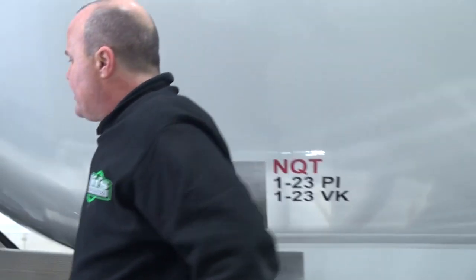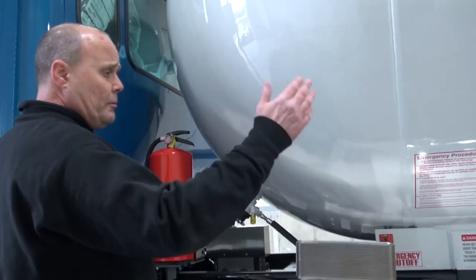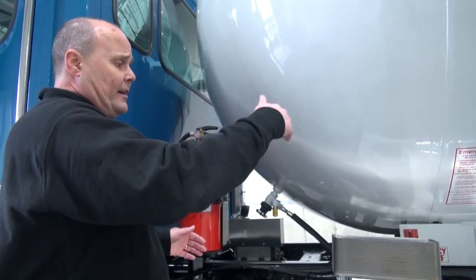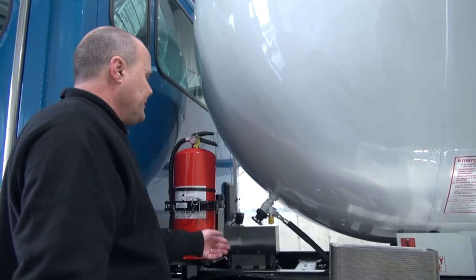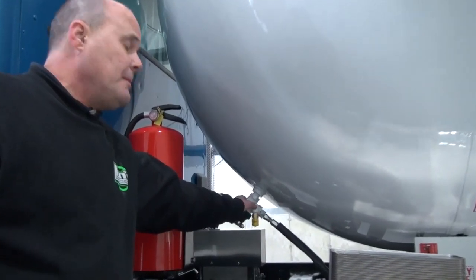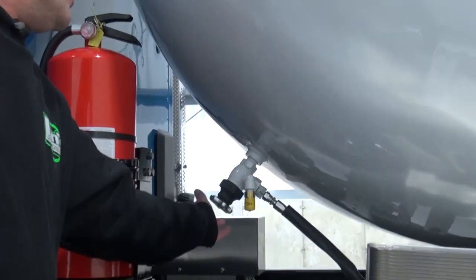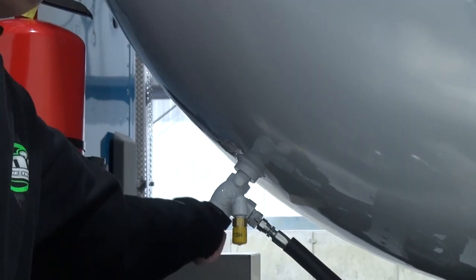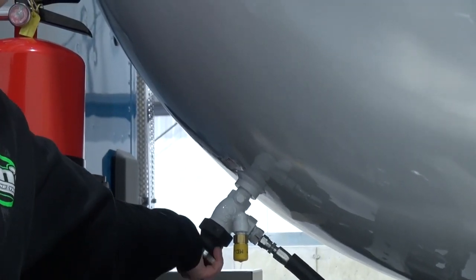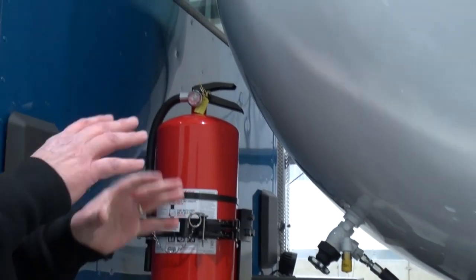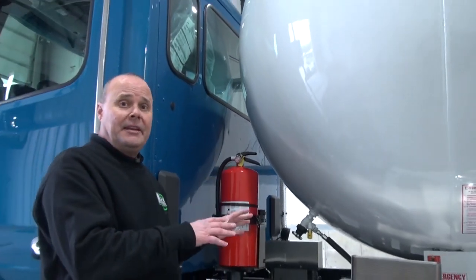Secondly, we'd want to come over to the head of the tank. So the liquid propane would travel from that ball valve, through that ball valve, to the heat exchanger, be vaporized, and then the vapor would return to the tank here. So we would want to shut this vapor globe valve off as well. So now we've isolated the propane part of the heat exchanger.